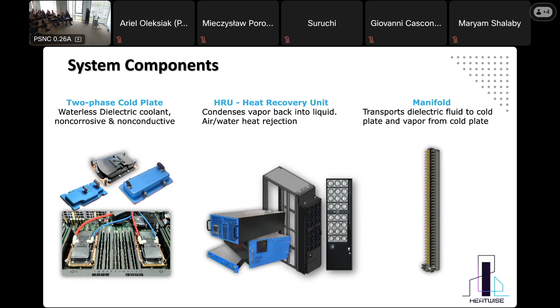So these are the cold plates, and this is how they are placed inside the server. Just an example - for an AI server it's much more complicated, with many more tubes inside. For heat rejection, we have two kinds: one where vapor is condensed back to liquid by air, in case the data center doesn't have a water facility, and when it does, we have units condensing the vapor back to liquid using facility water. And this is the manifold distributing and collecting the vapor.